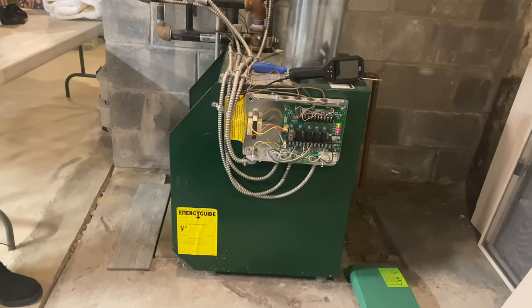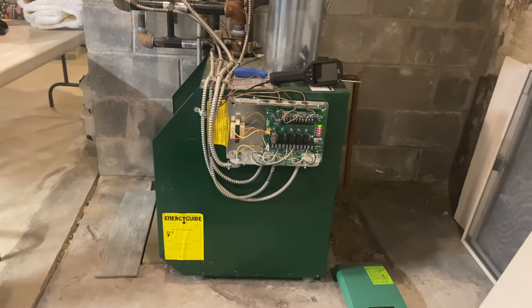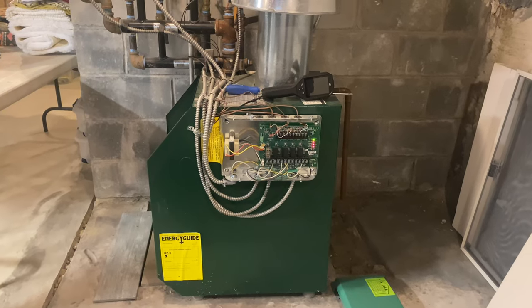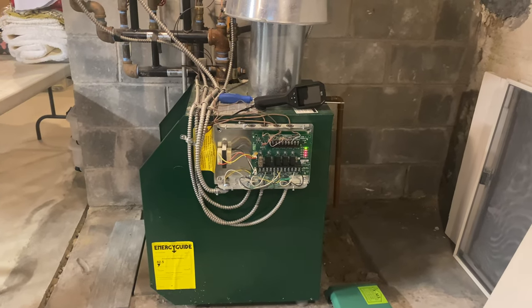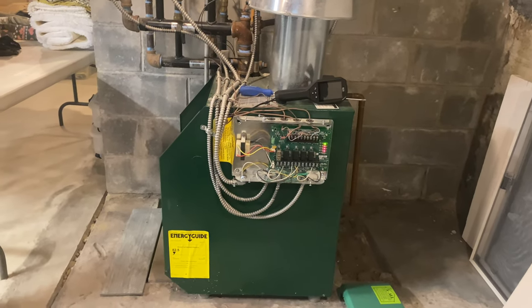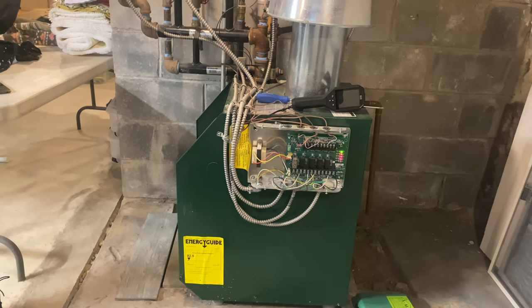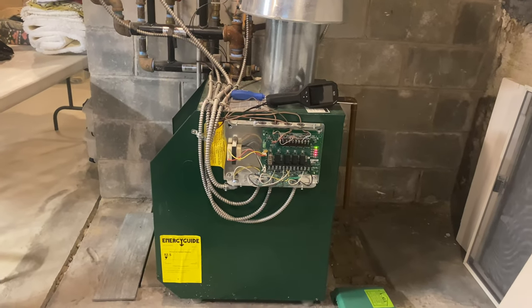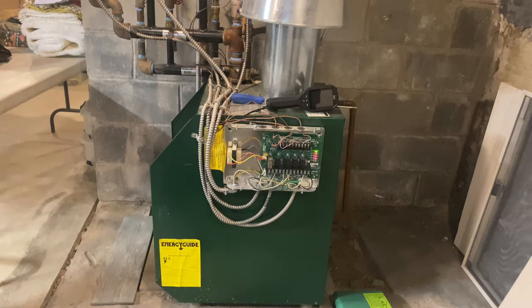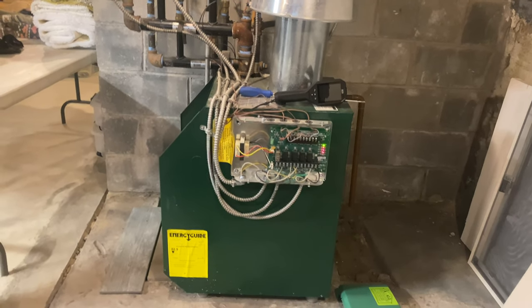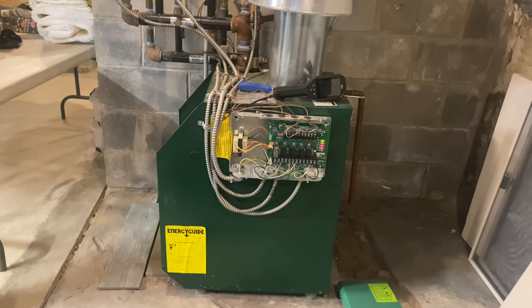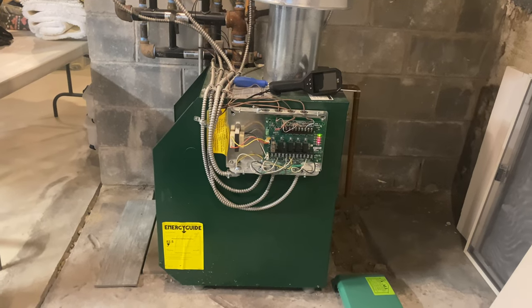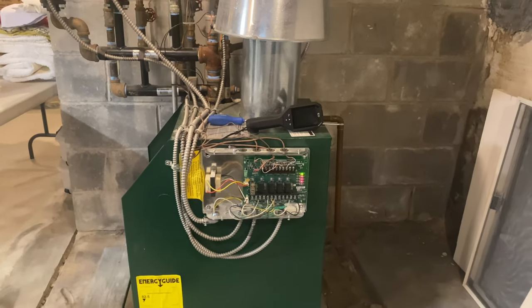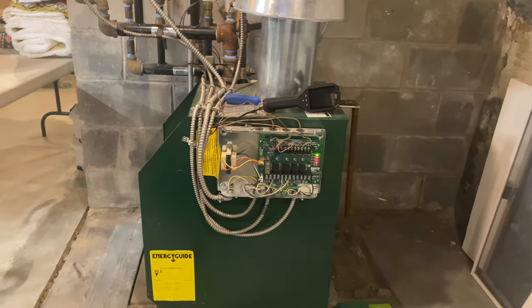Now, there are certain things we use these days called outdoor resets and things like that, which modulate the boiler temperature to maximize efficiency. Basically, the outdoor temperature justifies the boiler temperature. So let's say it's 20 degrees out, the boiler's at 190 degrees, or lower. It's at 180, which is the max, really, that it should be, because it's not a steam boiler, it's a hot water boiler, which is generally 180 degrees.